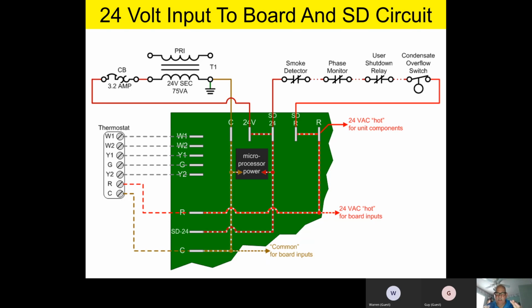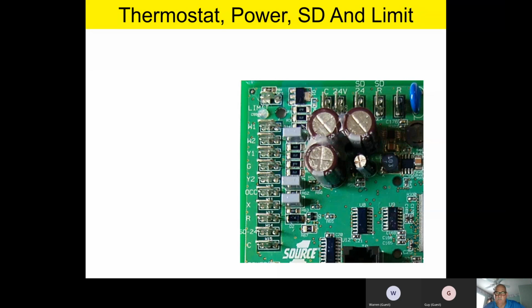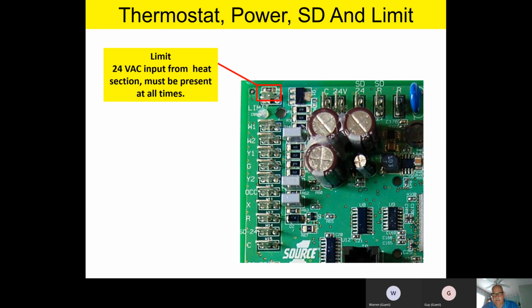Let's blow that section of that board up again that we talked about a minute ago into a larger slide here. So starting at the upper left-hand corner of this section of the board, you're going to notice there's a limit. It says limit. Now, it should be noted that's 24 volt input from the heat section, and it has to be present at all times. This is kind of an interesting point, because let's say it's in the dead of summertime and you're in the cooling season. Why in the world would that limit have to be closed? Well, it's a safety limit that's going to be monitored year round. And so you have to have 24 volt on that limit from the heating section to prove that the heating section doesn't have an open limit. Even if it's in the cooling mode, that still has to have 24 volt on it at all times.